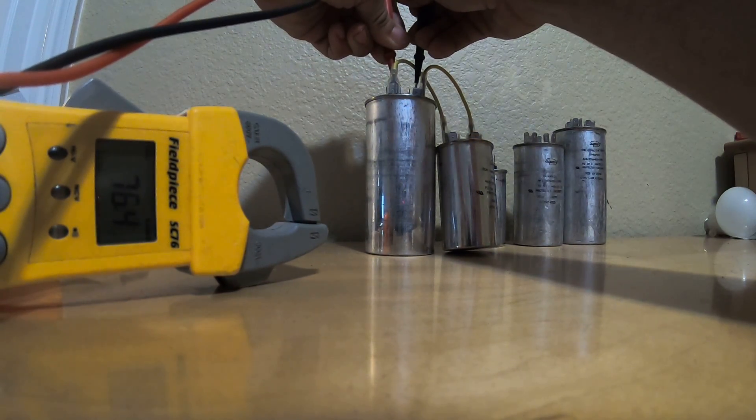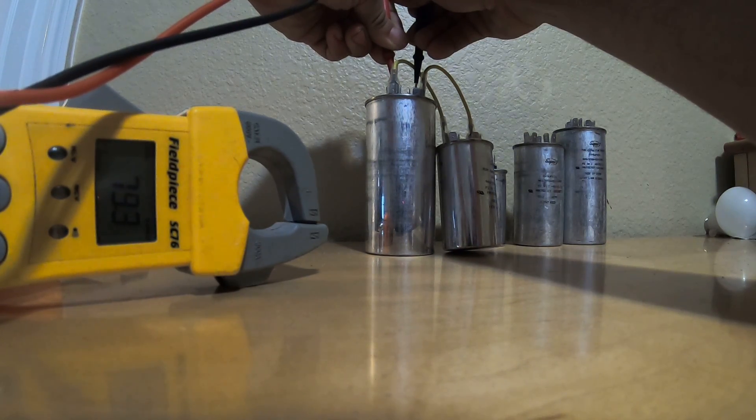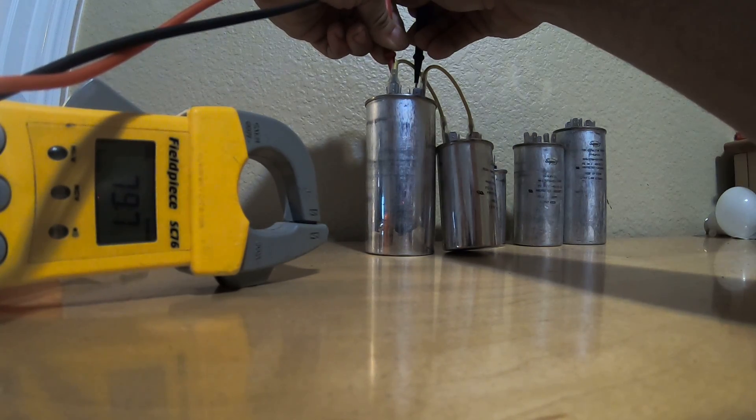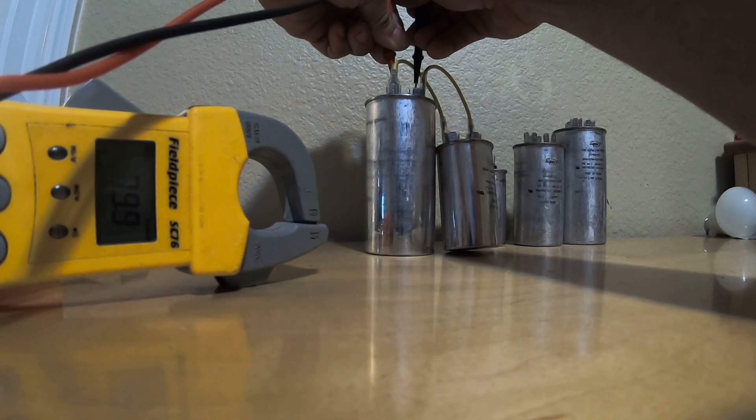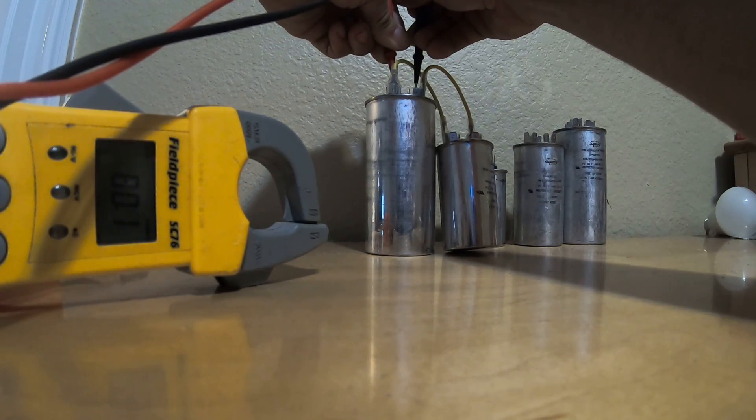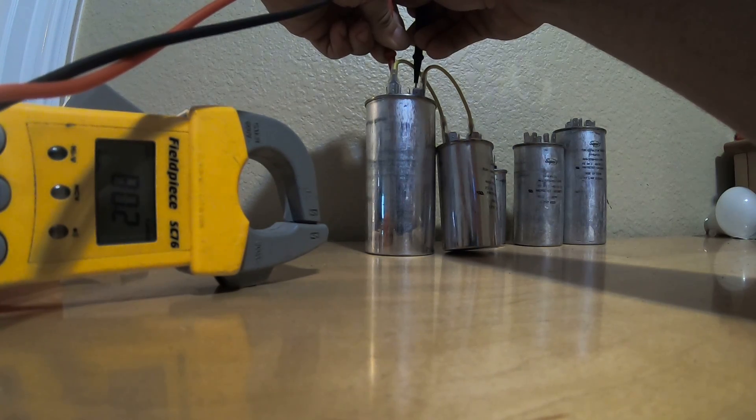Now all you have to do is hook this capacitor up like normal. Forget that these are even here. If you want to test it first, just go from common to Herm and you should read 80 microfarads. You know what, I'm going to redo this video too so y'all can see a little better. Actually, I'm going to do another video to show you how to wire up a PSC blower motor, which stands for permanent split capacitor blower motor at 115 volts. I don't know if y'all can see that, it's showing 80 microfarads.